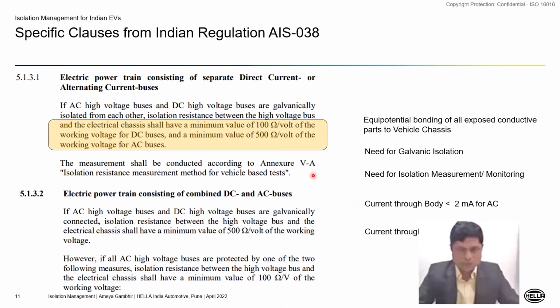By the way, the standard also talks about, or in other words, I have derived the currents based on the standard. So when we are talking about 500 ohms per volt, we are talking about less than 2 milliamps of current allowed through the body for AC. And when we are talking about 100 ohms per volt of isolation resistance, we are talking about less than 10 milliamps of current that should be allowed to flow through the human body. This is in correlation with what we just saw in the international standard.